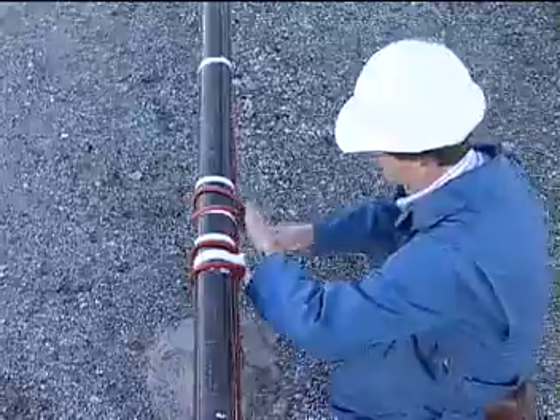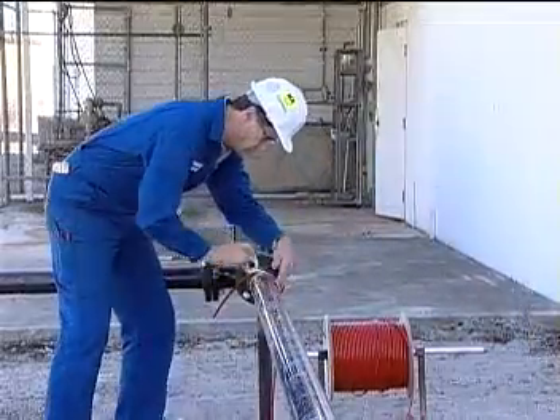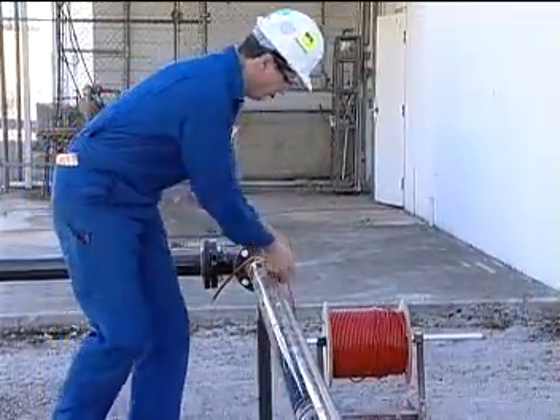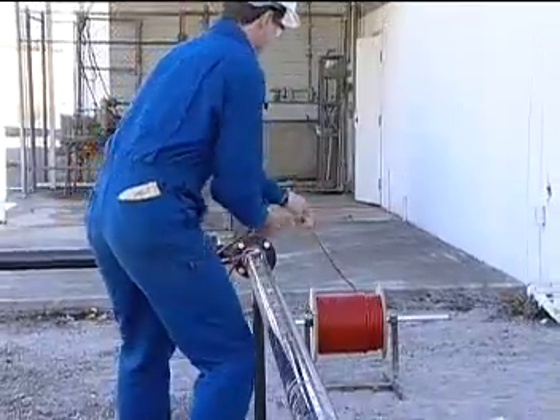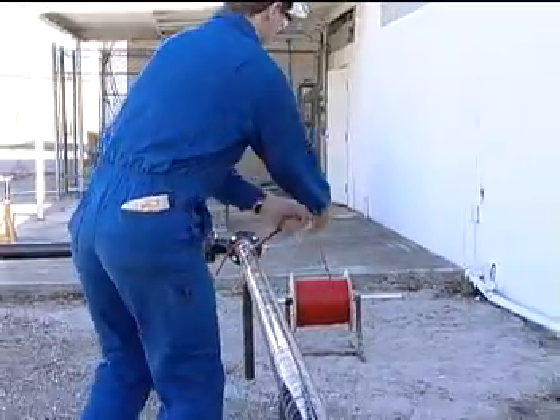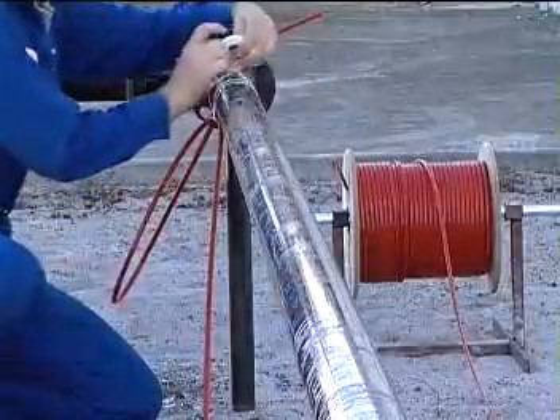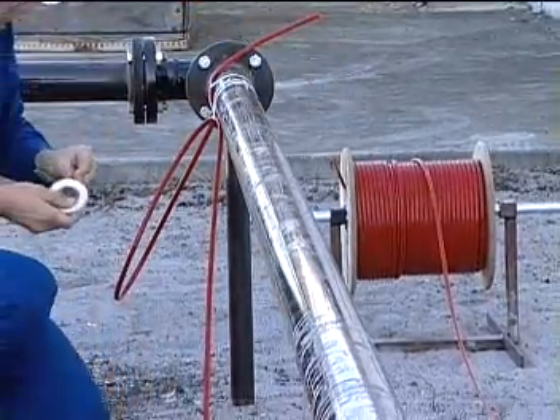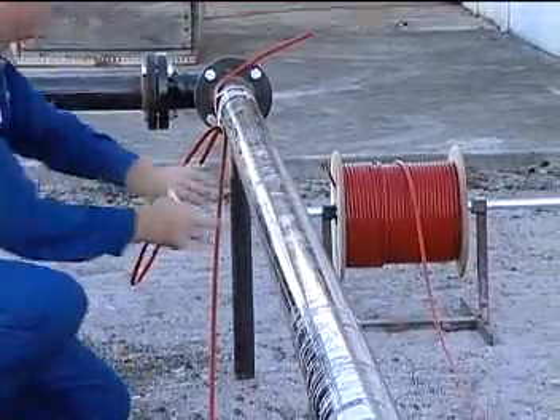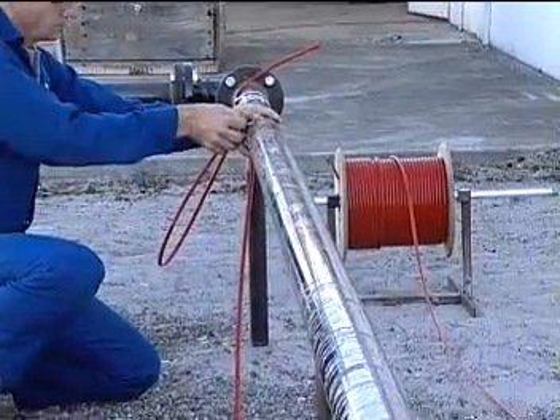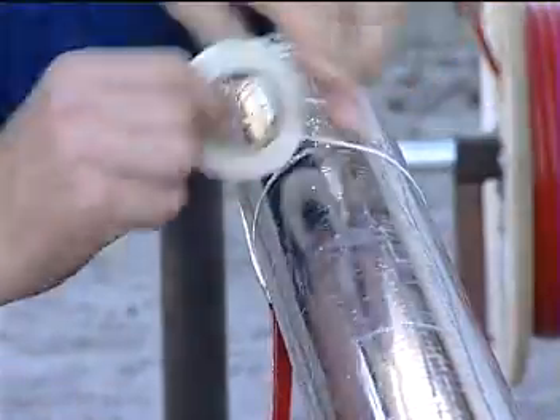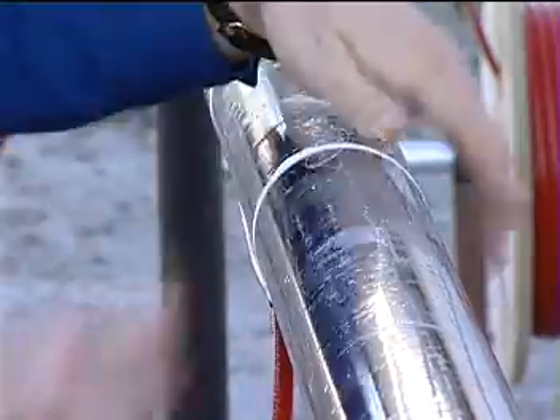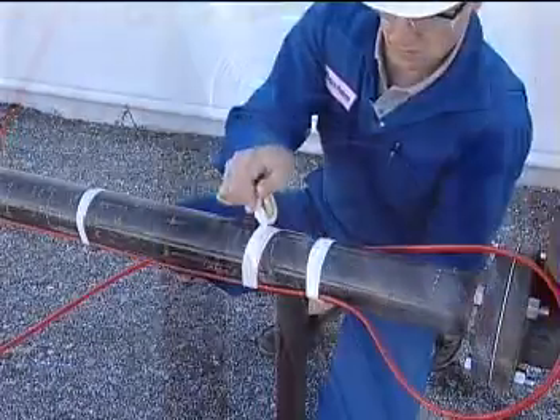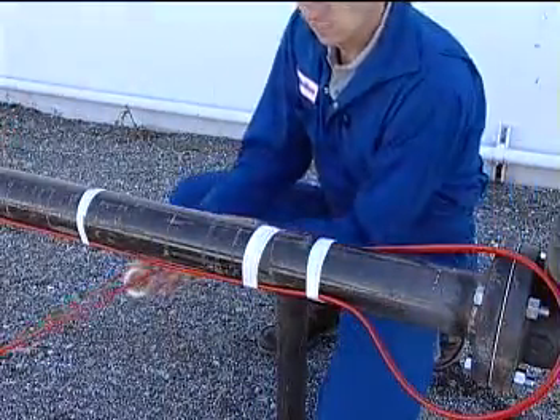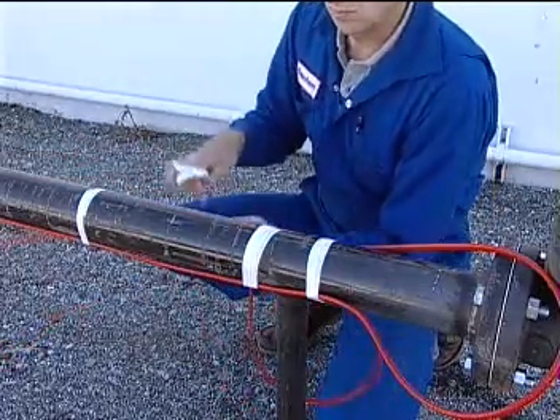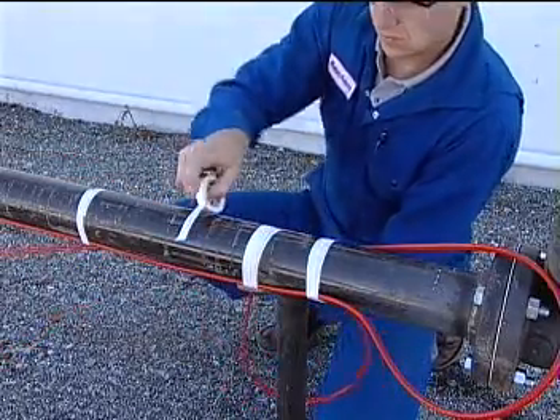If you're using 1 reel instead of 2, first attach the end of the heating cable to the pipe next to the cable reel. Then pull the cable in a large loop down the piping run. As you move, attach one side of the cable to the pipe, leaving the other side loose. Again, leave extra cable for the heat sinks. Also, leave an extra loop from each cable on the serviceable heat sinks, such as valves and flanges. When you reach the end of the run, leave extra cable for the end seal. Then, work the remaining side of the cable back toward the start.